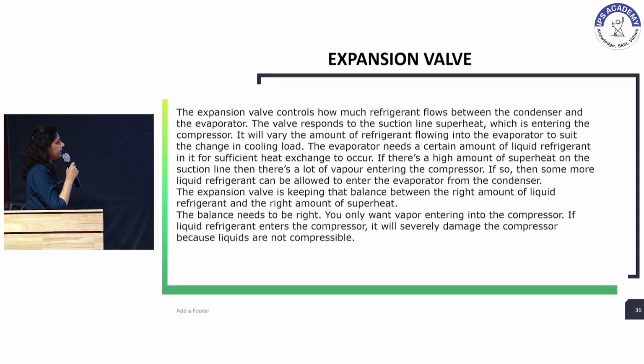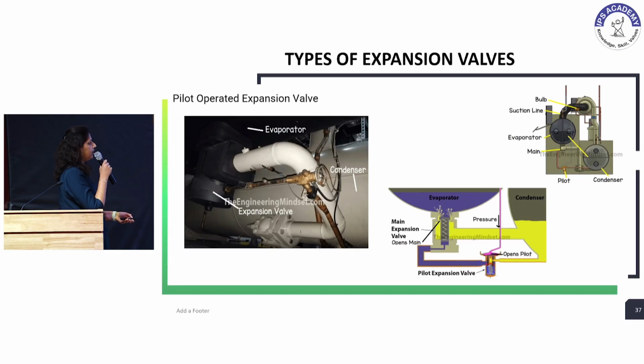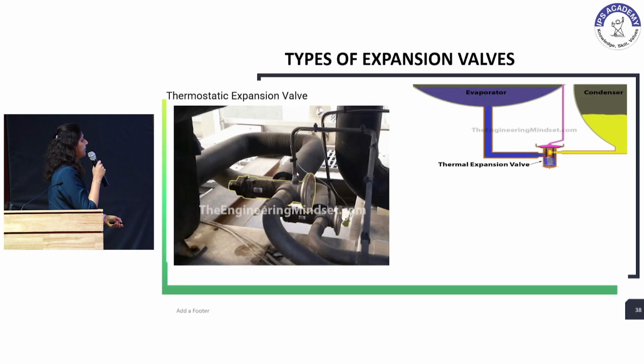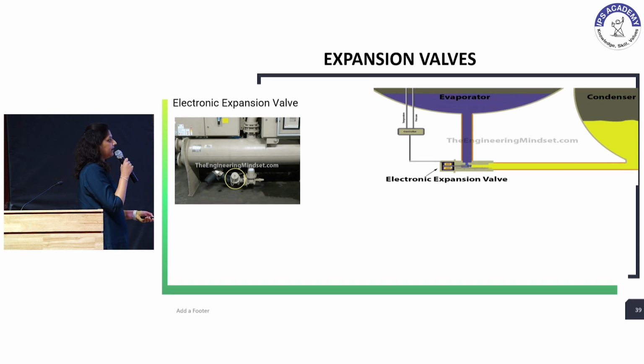The fourth and the major component of the compression cycle is the expansion valve. This controls how much refrigerant flows between the condenser and the evaporator. And it is very important to design this in a proper way because this helps us to also attain the maximum efficiency of the machine. There can be different types of expansion valves. One is the thermostatic expansion valve, the other is the electronic expansion valve. So here you see the picture of the thermostatic expansion valve. This was an older way of using the expansion valve where it used to work on a spring type basis. Now majorly we are using a lot of electronic expansion valves. This is the electronic expansion valve which senses in accordance to the performance of the machine and opens the refrigerant flow in that context.